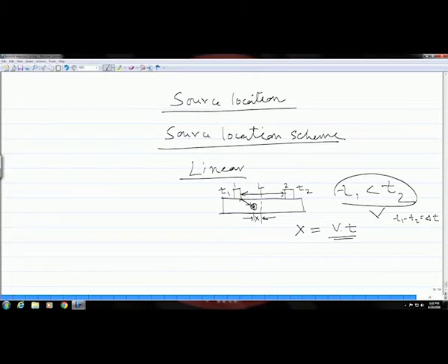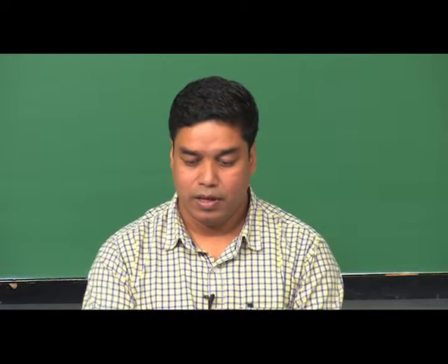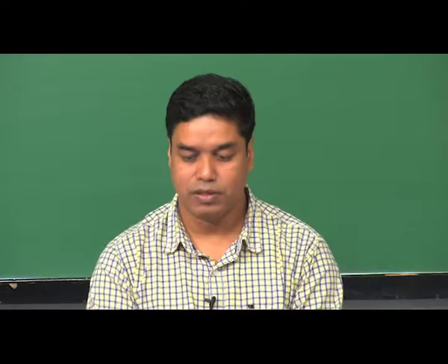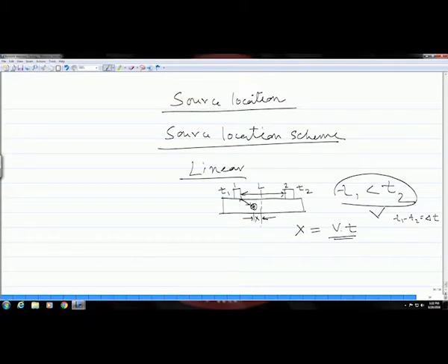Okay. So, this is how you will get an idea about the zone or the location from where these acoustic emission signals are coming out with respect to this central line. Okay. So, this is if you have a linear system. So, this is a linear location technique.